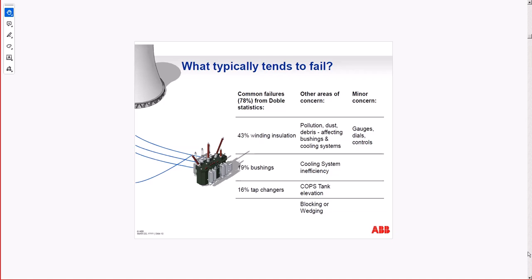Typical trends to fail. Well, Doble, which is one of the most important manufacturers for testing, found 43% of the failures come from the windings of the transformer, 19% from the bushings of the transformer, and then 16% from the tap changers, especially if they are load tap changers. Okay, that ends up at 78%. Now IEEE and others may have slightly different percentages, but the difference is not significant, it's basically in the same ballpark and the same order, so that doesn't change.